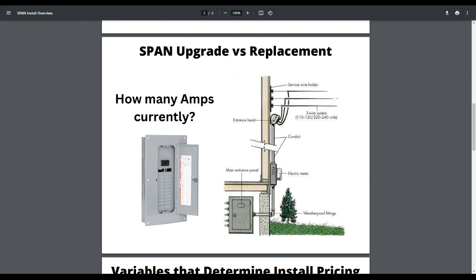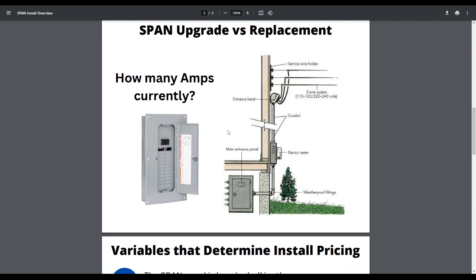Now if you have a 100 or 150 amp panel, we need to do what's called an upgrade to 200 amps. What's required is not only replacing the panel itself, but all these other components from the utility connection: the service head, the service entrance cable, the meter itself, and the service entrance into the back of the panel. All of that needs to be replaced to meet a 200 amp sized requirement. So if we're going from 100 or 150, we need to replace this entire system, which is obviously more complex, more labor, more material involved. So that's where we always start as well.